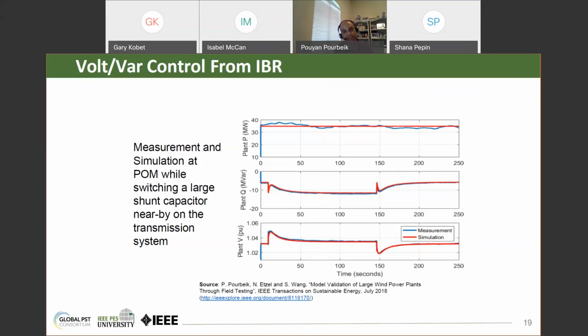Then you can clearly see that immediately there's a little spike down in Q, that's the turbines immediately reacting, pulling Q down, and then the plant controller, as a second layer of control, slowly brings the voltage back to where it started. And then when the capacitor switches again, so we switched it in, now we switch it back out, the opposite happens. So you can see clearly that you have both very fast control given by the turbines and then a slower tier of control, vernier control, at the plant level. So it can be done.